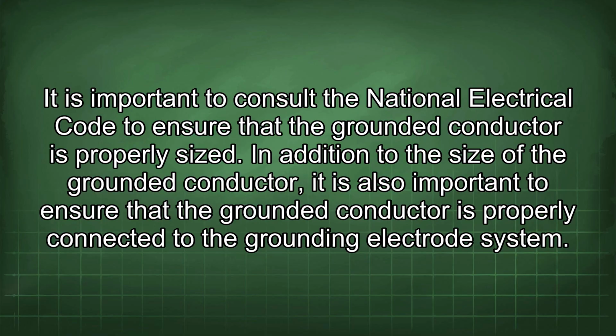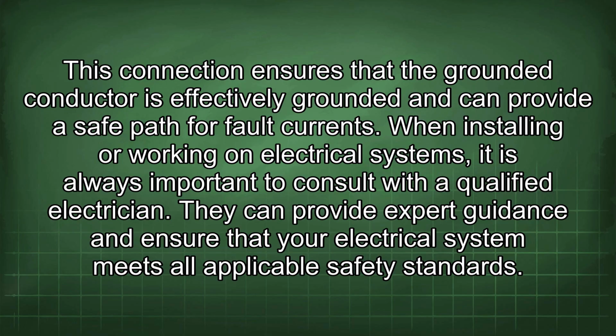In addition to the size of the grounded conductor, it is also important to ensure that the grounded conductor is properly connected to the grounding electrode system. This connection ensures that the grounded conductor is effectively grounded and can provide a safe path for fault currents. When installing or working on electrical systems, it is always important to consult with a qualified electrician. They can provide expert guidance and ensure that your electrical system meets all applicable safety standards.